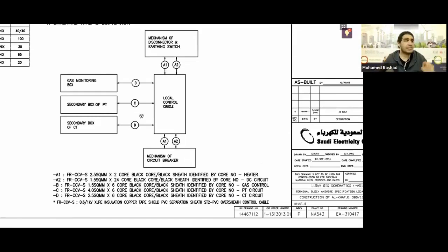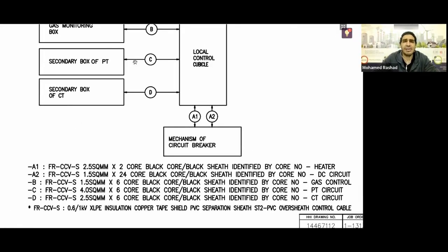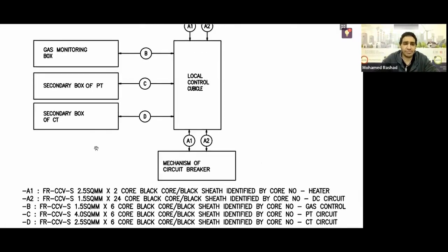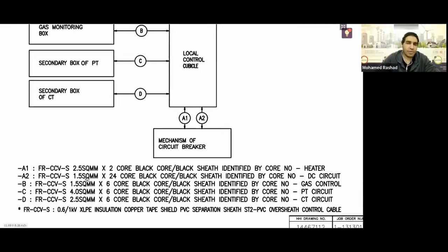However, the CT circuits that are coming to me from the GIS itself and reaching my cell are considered external wires, external wiring not included within my panel. In this case, what will these wires be like? If you look at the CT cable, you will find cables of 2.5. Okay, great. And for the C, which is the VT circuits, you will find 4mm cables. As for the gas gauges, the SF6 gas pressure meters, they are 1.5mm. All these cables will be 6 core. And we wrote this for the gas control, this for the VT circuit, and this for the CT circuit.